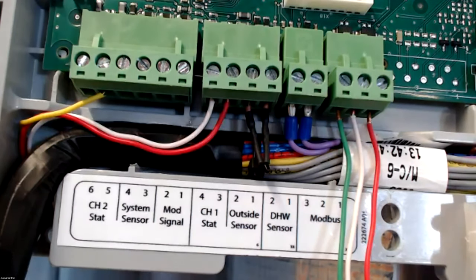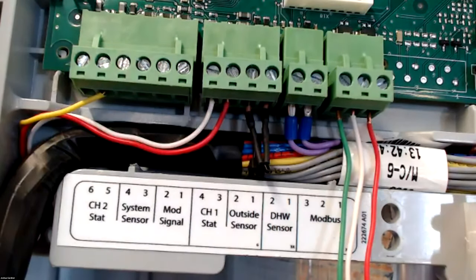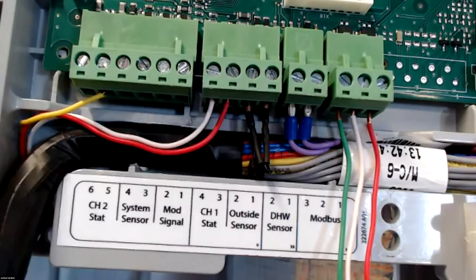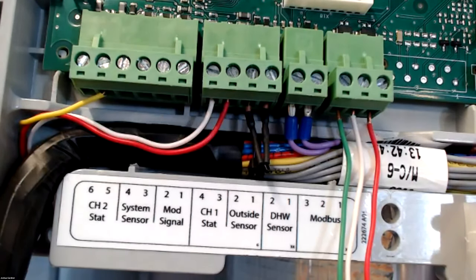The one thing to note in that is when you go to set up your domestic, if you're using an indirect, it's going to ask you the first question, thermostat or sensor? If you use the aquastat, select thermostat. If you're using the sensor, select the sensor. So if you don't select that right, you can have issues with the domestic. Just make sure that's set correctly.